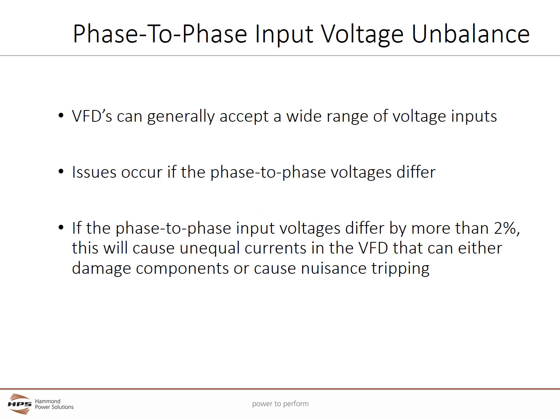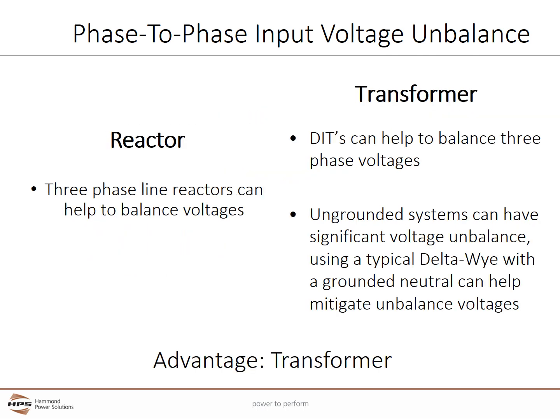Phase-to-phase input voltage imbalance. While VFDs can accept a wide range of voltage inputs, unbalanced three-phase voltages occur for several reasons. They are especially prevalent in older and rural electrical systems which use a three-phase open delta circuit, which uses 2 single-phase transformers instead of 1 three-phase transformer or a set of 3 single-phase transformers which are banked. Open delta circuits are also often ungrounded. Ungrounded circuits may also be found in mobile machinery and marine applications. If the phase-to-phase input voltages differ by more than 2%, this will cause unequal currents in the VFD, which can either damage components or cause nuisance tripping.